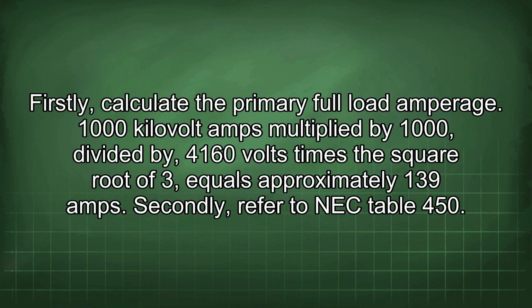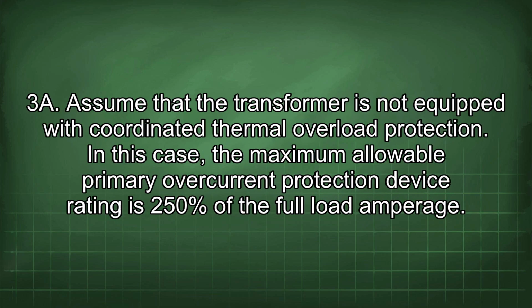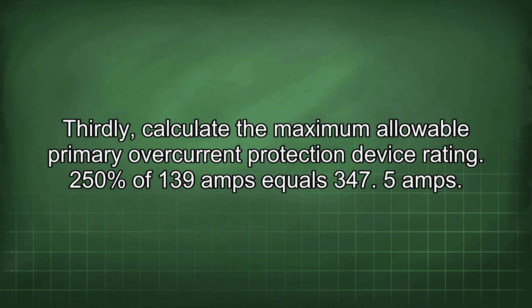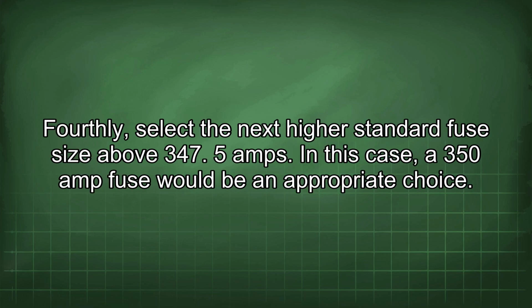Secondly, refer to NEC Table 450.3a. Assume that the transformer is not equipped with coordinated thermal overload protection. In this case, the maximum allowable primary overcurrent protection device rating is 250% of the full load amperage. Thirdly, calculate the maximum allowable primary overcurrent protection device rating. 250% of 139 amps equals 347.5 amps. Fourthly, select the next higher standard fuse size above 347.5 amps. In this case, a 350 amp fuse would be an appropriate choice.